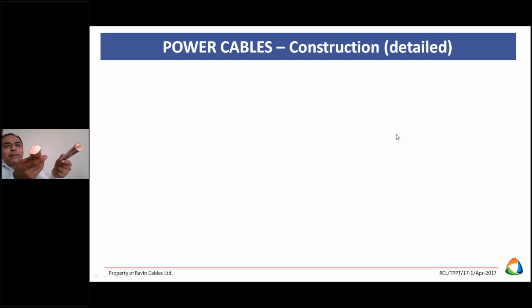Now, round conductor versus shaped conductor - why is one round and one shaped? In LT cables, we use shape conductors in case of multi-core cables. But for single core cables, we definitely require round conductors, not shape or square conductors. The reason is that electrical potential or electrical field intensity is highest at sharp points, and sharp edges create such points. Higher electrical intensity at these points requires more insulation to protect the system.